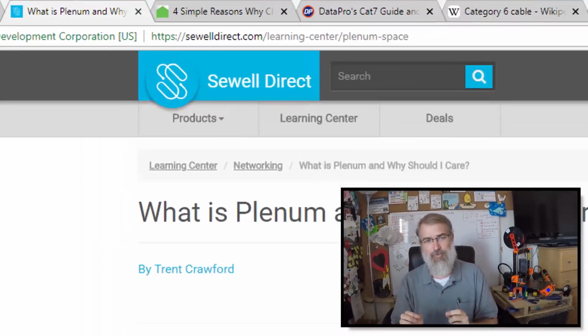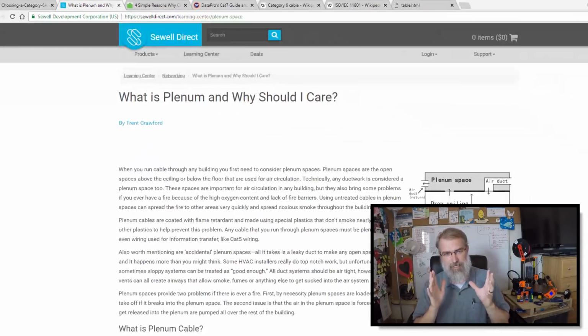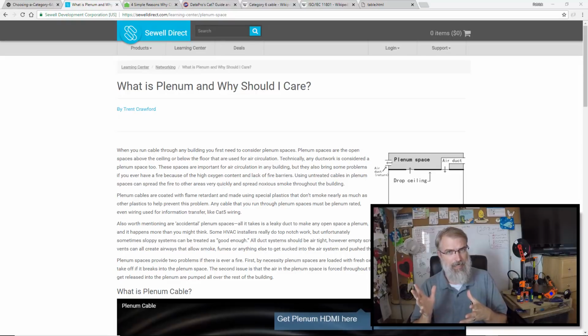Okay, first let me go into plenum because that might be important in your situation. You can go to this website, sewelldirect.com, Learning Center Plenum Space, to see what plenum is and why you should care. The short answer really is plenum is a different coating, and you can have a plenum Cat5e, a plenum Cat6, a plenum Cat6A. Plenum is just the rubber coating on the outside, and it's really a rating. It means it's more fire retardant, and it also doesn't give off noxious fumes. And there are some important reasons why you should care about that.